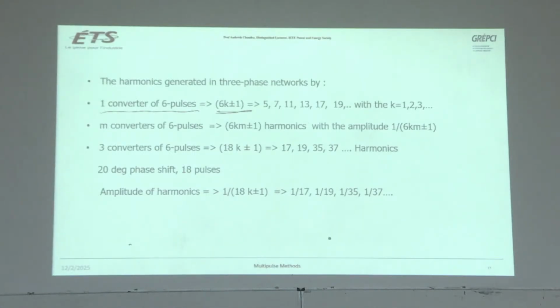then this is the formula for what harmonics it will generate. For k equal to 1, the 5th, 7th, 11th, 13th, 17th, 19th harmonics are generated with one converter of 6 pulses. If you are having m converters of 6 pulses, this equation can be written like this, and the amplitude is this. So if you have 3 converters, for k equal to 1, 6 multiplied by 3, so 18k plus minus 1. So if k is equal to 1, you have a minimum of the 17th harmonic.